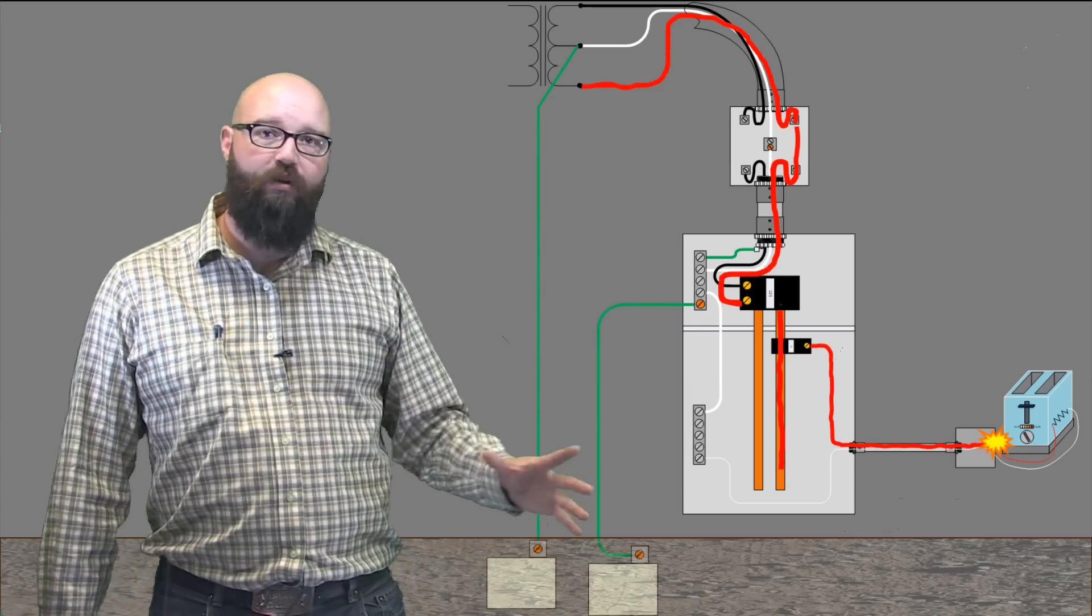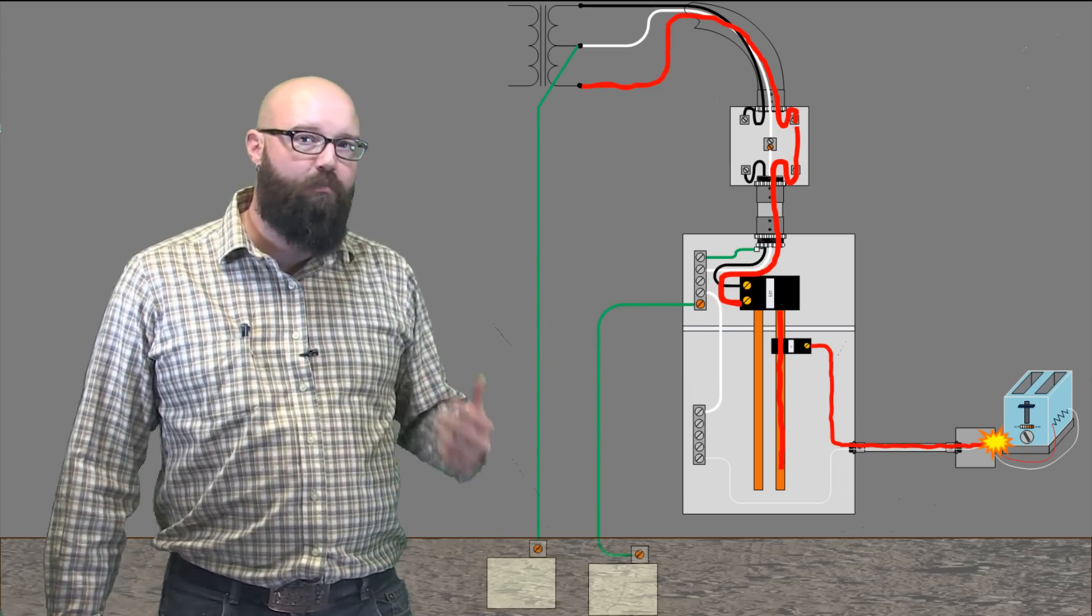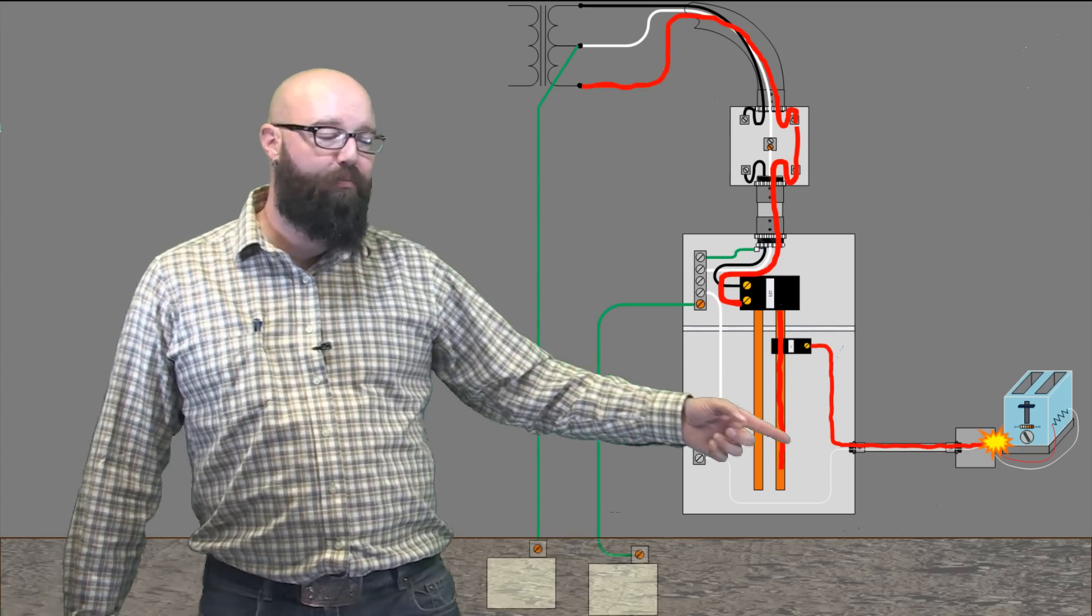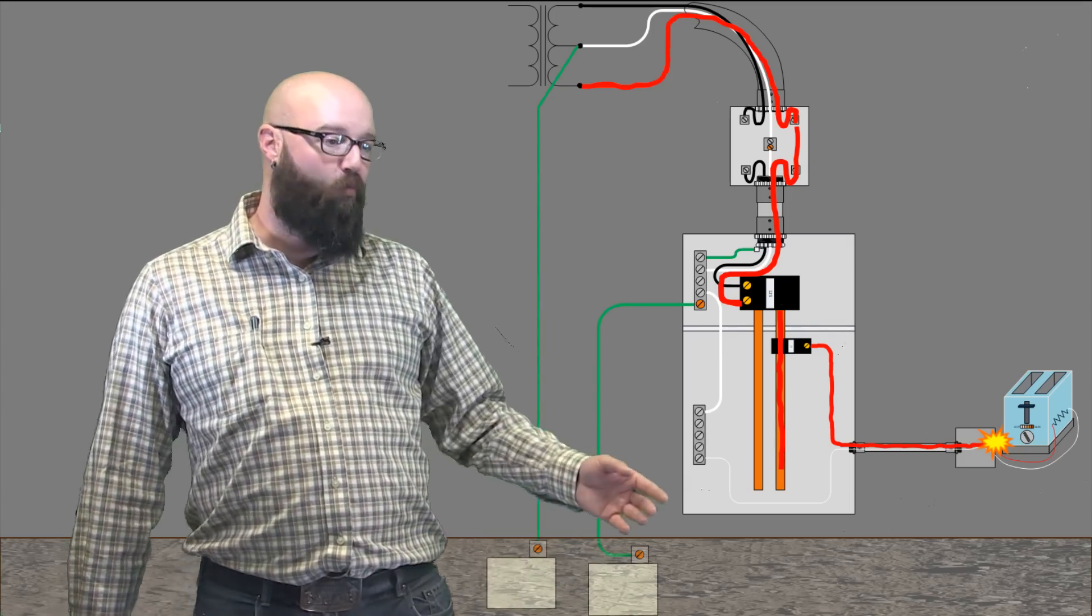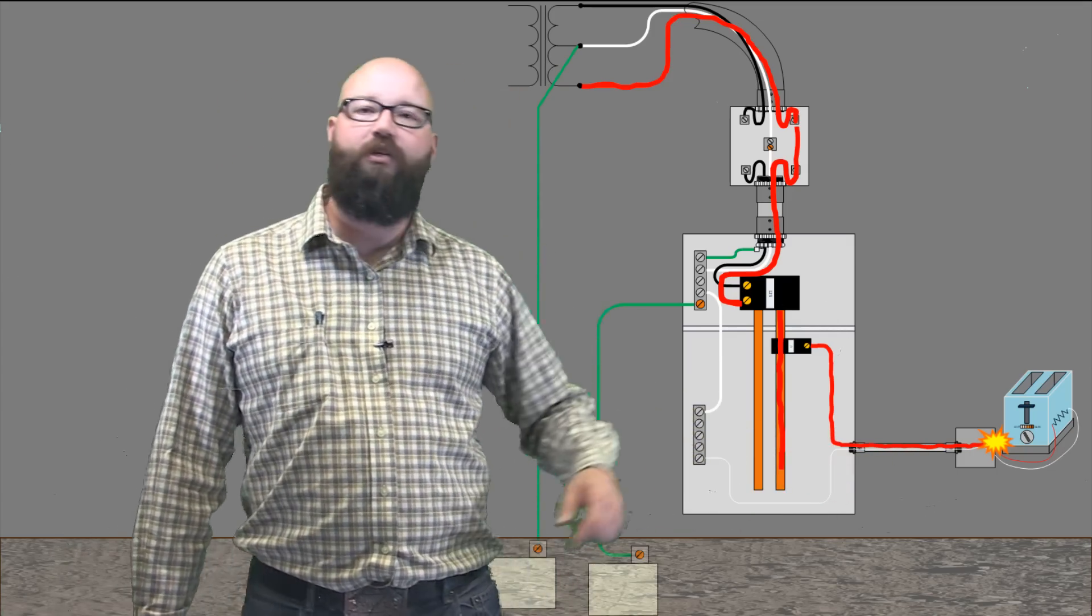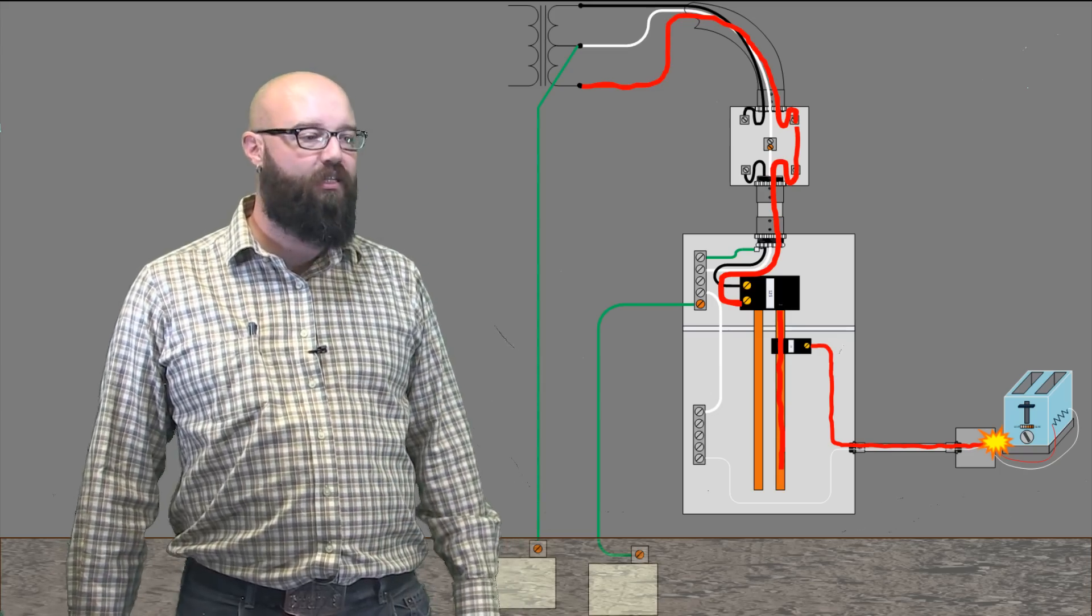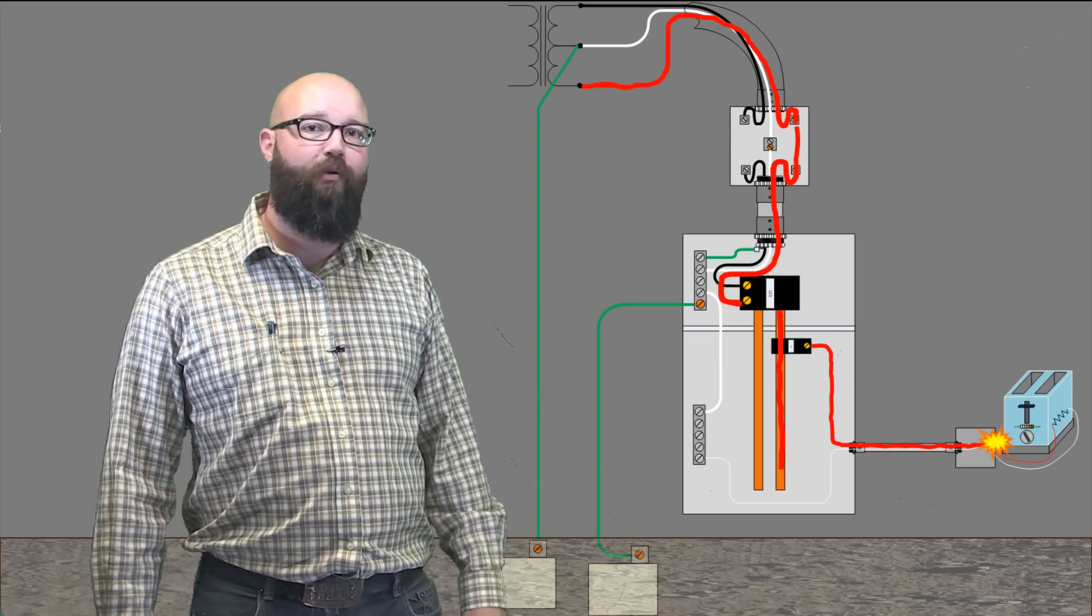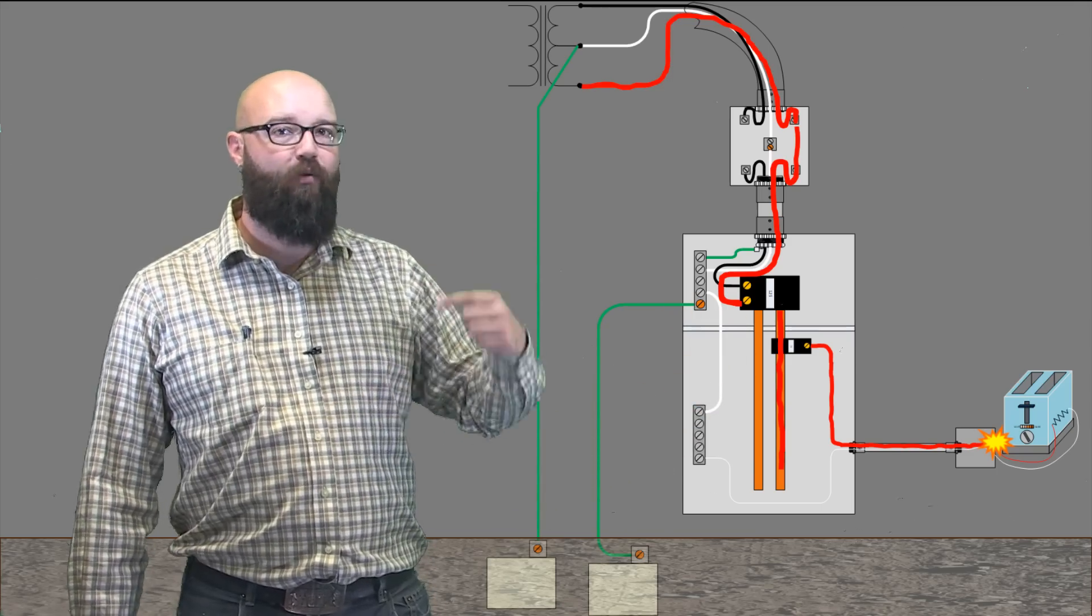Now our whole grounding and bonding system is designed to create a low impedance path. That low impedance path consists of all of our metal boxes, all of our metal raceways. We're making sure that all of these set screws and all of these lock nuts are done up tight. It's all part of our bonding system. If it's all bonded properly, it gives us sufficient low impedance path back.